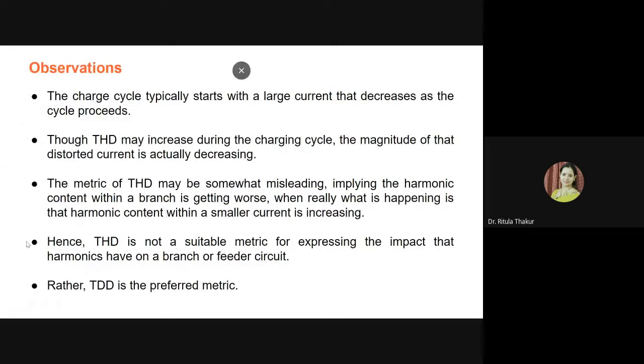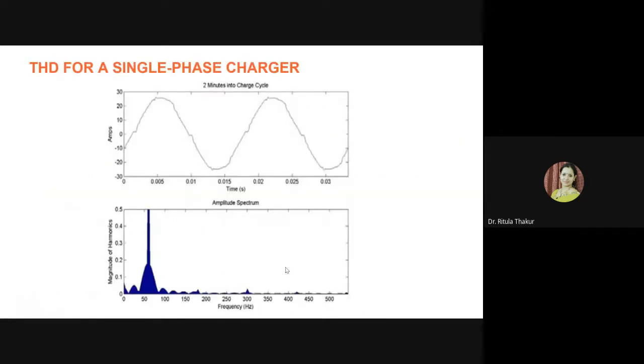So mostly what we do is we take care of total demand distortion as the preferred metric for expressing the impact of the harmonics on the branch or the feeder circuit. Okay, now these are the individual results. Although there were many readings which were taken, this shows the THD for a single phase charger during the beginning of the charge cycle.